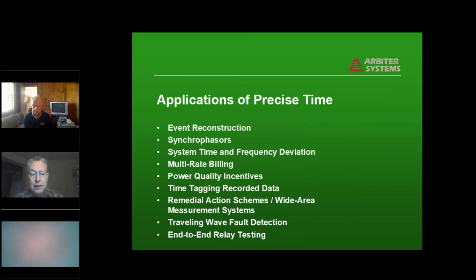Remedial action, wide area measurement schemes. These are things that allow the system to be protected instead of, most protection operates to protect a single asset, a generator or a transmission line or something like that. Remedial action schemes based on wide area measurement systems are used to protect the overall operation of the system itself by doing something that you wouldn't necessarily suspect necessary on the basis of a single asset. Traveling wave fault detection used to precisely locate a fault, generally to within a couple of towers, to assist with dispatching repair crews.